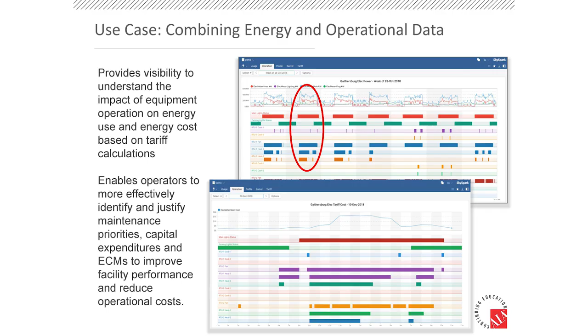Should it be running? No, we were supposed to soft start equipment. Let's go look at the schedule, or the specification of the control system. It was specified that we should soft start the second stage of equipment. I think we found a finding that needs to be investigated, because maybe nobody actually implemented the soft start routine. This quickly leads us to understanding those types of issues in the commissioning of systems, by correlating equipment operation against our energy curves automatically.